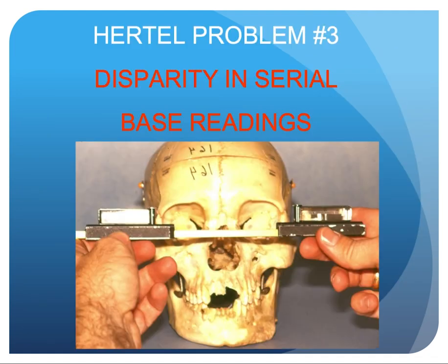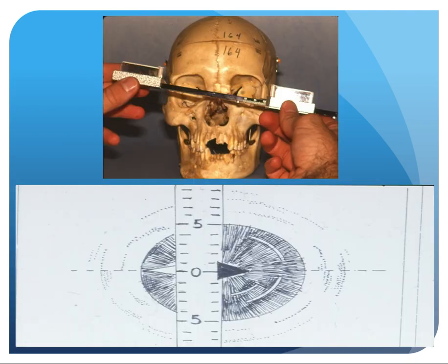Hertel problem number three: there is disparity in serial-based readings. With the Hertel instrument placed against the skull, the flange can be positioned either inferior, superior, lateral, or medial — so it will not be in exactly the same place as in the first reading. With the Naugle instrument, the black arrows align in the mid-pupil with the medial wall of the vertical strut placed exactly in the mid-pupil, ensuring the same spot in serial measurements as in the original.